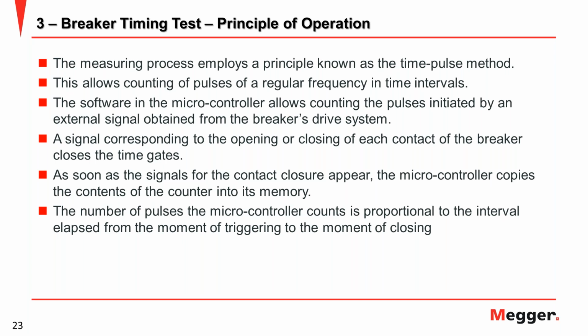The measuring process employs a principle known as the time pulse method. This allows counting of pulses of a regular frequency in time intervals. The software in the equipment tester, in the microcontroller, counts the pulses initiated by an external signal obtained from the breaker's drive system. Then the signal corresponding to the opening or closing of the breaker contact closes the time gate. As soon as the signal for the contact closure appears, the microcontroller copies the content of the counter into its memory. So the number of pulses the microcontroller counts is proportional to the interval elapsed from the moment of the trigger to the moment of closing.